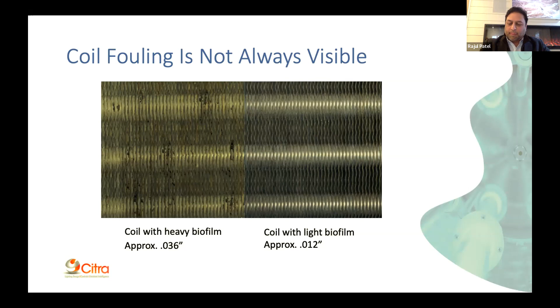There's several studies that were done on how effective manual coil cleaning is. Typical manual coil cleaning involves spraying chemicals and using pressure washers. These studies, including an ASHRAE study, have found that the biomatter is actually more compacted towards the center of the coil, which is reducing the airflow and therefore the performance of the system.